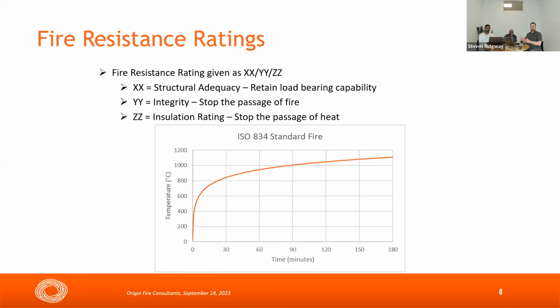One thing to note, those numbers aren't based off a real fire, because every fire is different. So we use time equivalence formulas to equate it to the ISO standard fire. That one's a benchmark. It gives you something to compare against. And so when you have fire rated structure and it's tested, they're tested against the standard fire. And so you know, is this good enough for this project? Yes or no.